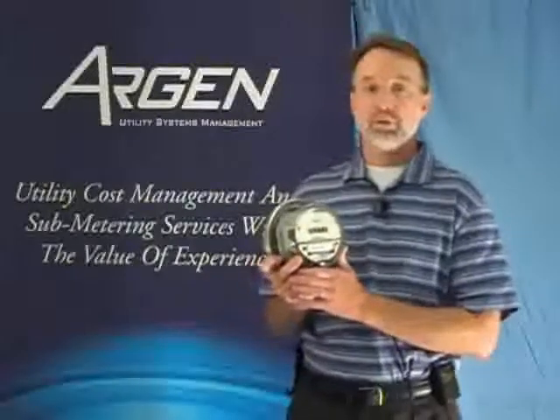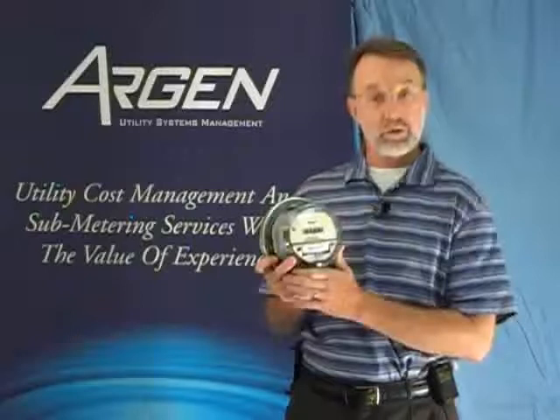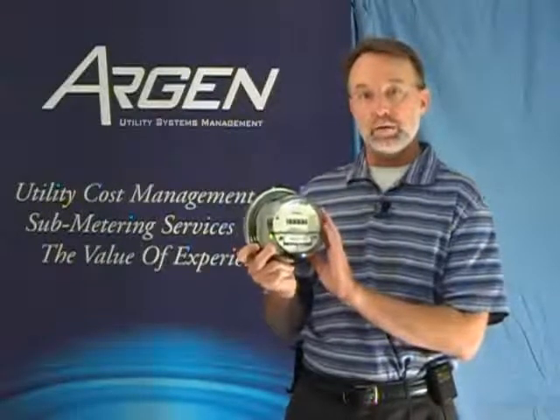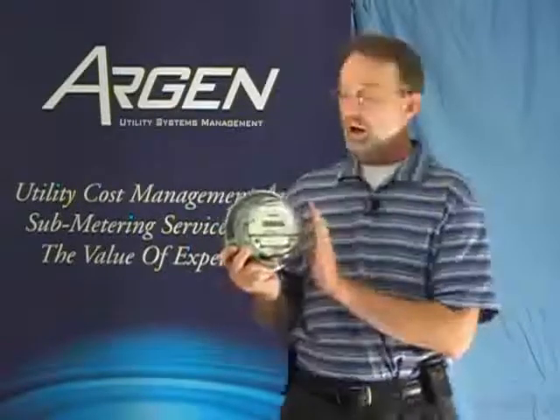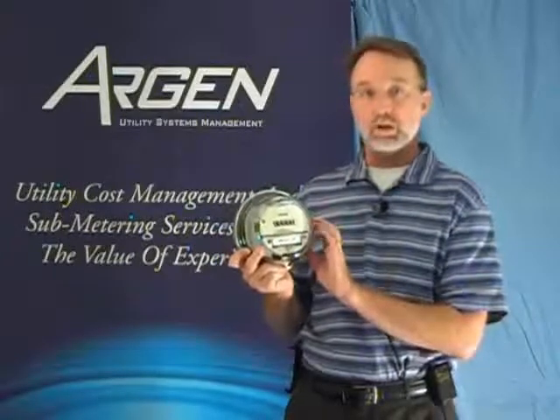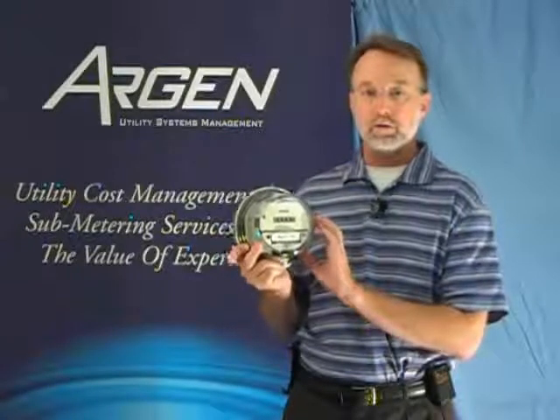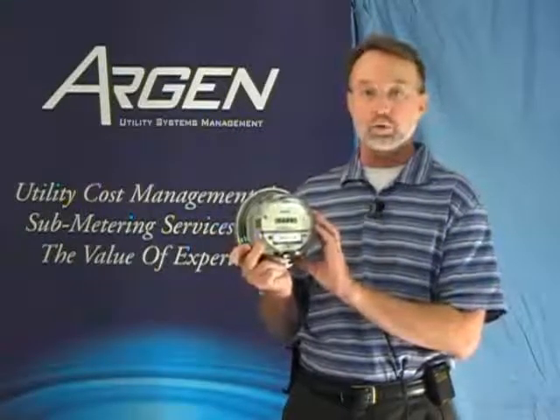For electric utility submetering, industry standard 240 volt single-phase meters are typically used for residential applications. These meters can be read in a variety of fashions. This is an example of a direct read visual meter where the meter reader actually walks up to the meter, visually takes the read off the dial, and punches that into a handheld data collector. Another method to read electric meters is to outfit this unit with a radio transmitter receiver and read the meter in the same fashion that water meters are read. A third method of reading electric meters is called power line carrier, where the meter read signal is transmitted over the electric supply line to an off-site data collection point.